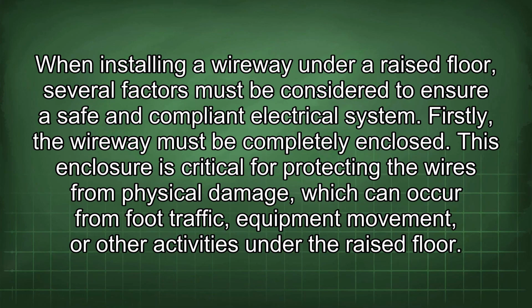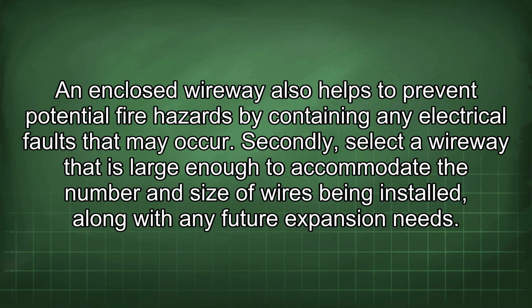When installing a wireway under a raised floor, several factors must be considered to ensure a safe and compliant electrical system. Firstly, the wireway must be completely enclosed. This enclosure is critical for protecting the wires from physical damage, which can occur from foot traffic, equipment movement, or other activities under the raised floor. An enclosed wireway also helps to prevent potential fire hazards by containing any electrical faults that may occur.